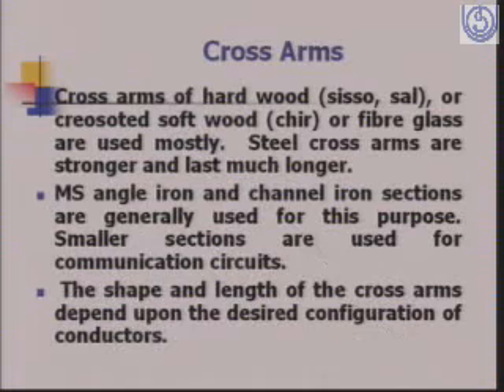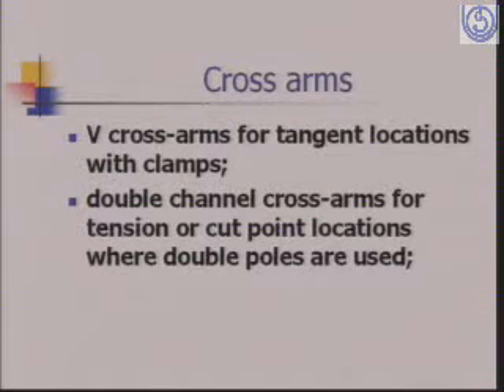Then we have the cross arms. They can be made of wood or fiberglass or iron, and steel cross arms are stronger and last much longer. MS angle iron and channel iron sections are also being used for this purpose, and the shape and length of cross arms depends upon the desired configuration of conductors, whether we are using vertical, delta or horizontal configuration. V cross arms are used for tangent locations with clamps, double channel cross arms for tension or cut point locations where double poles are used.